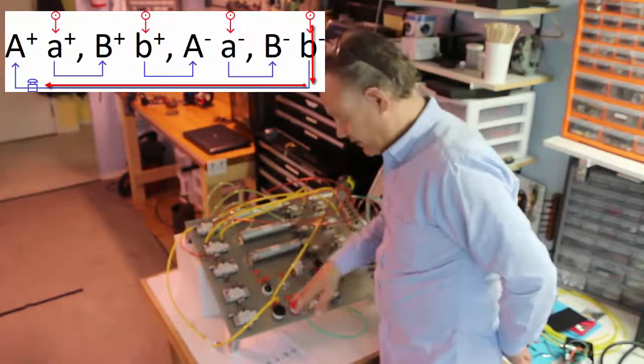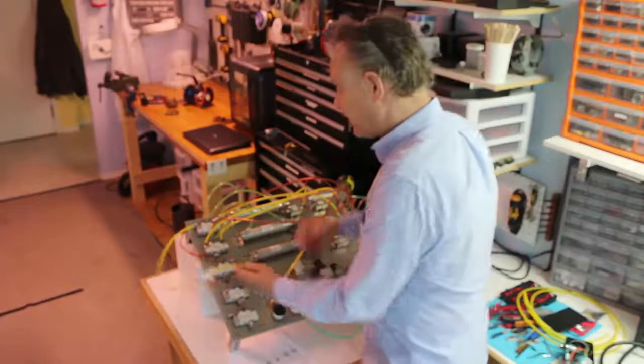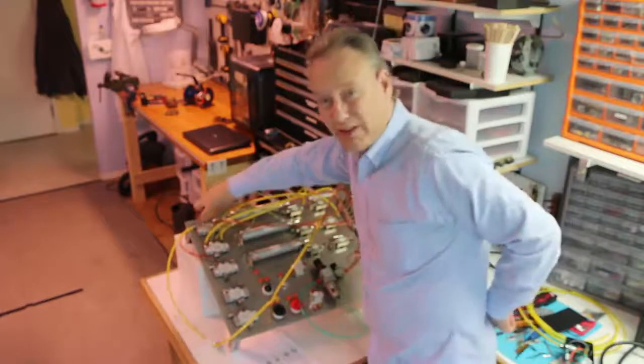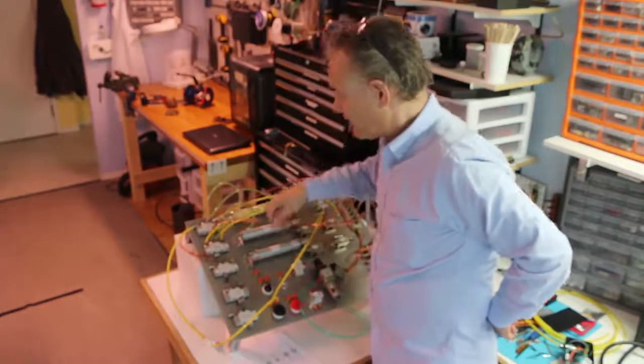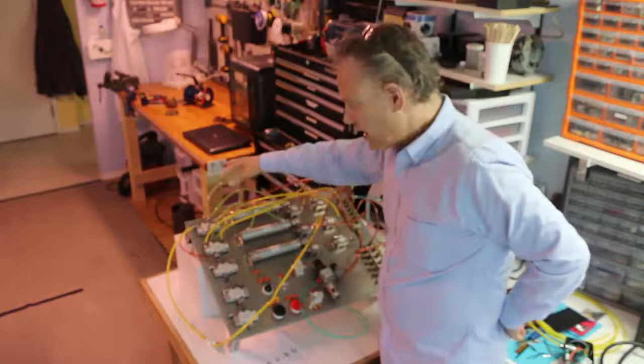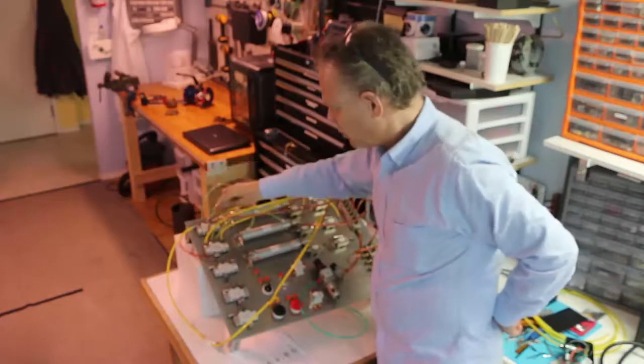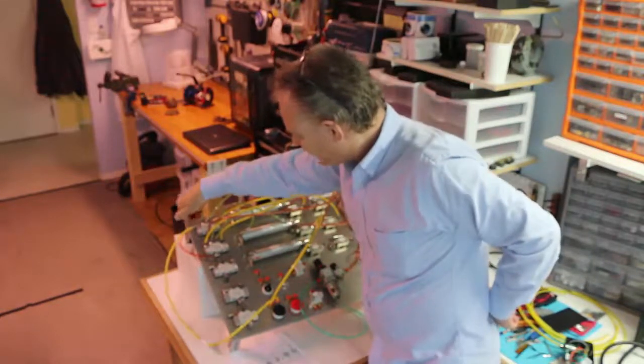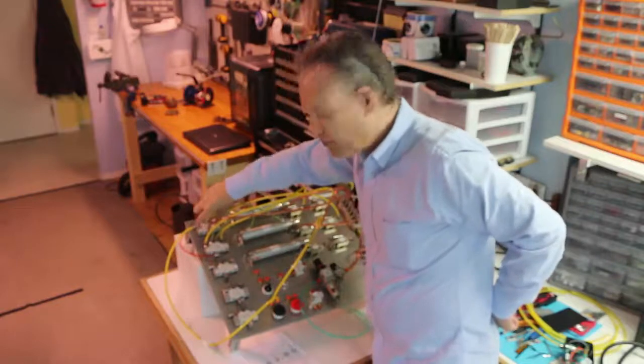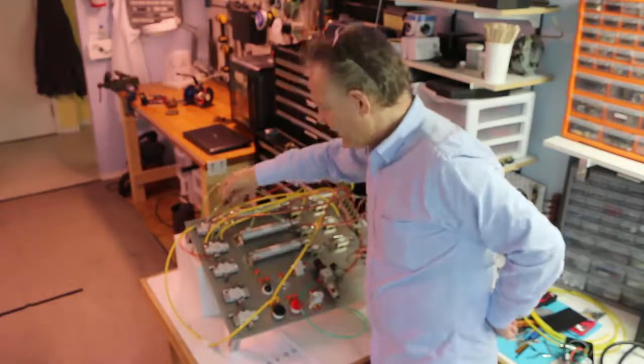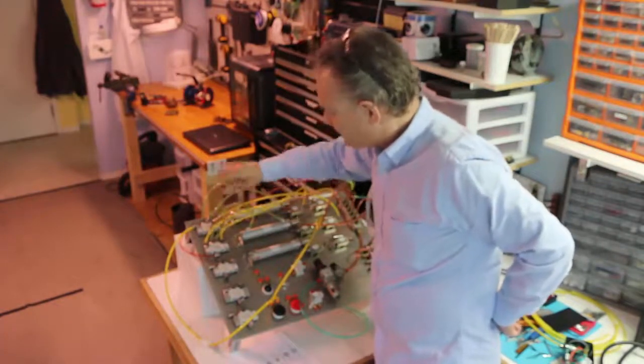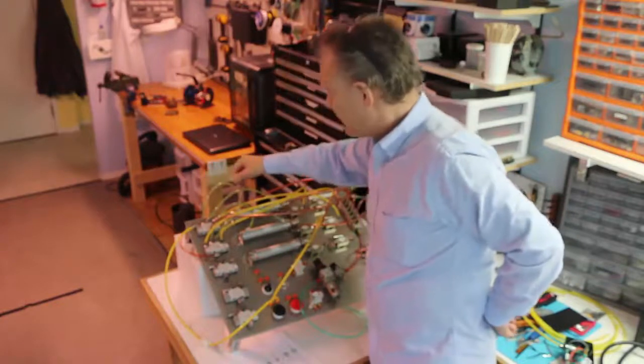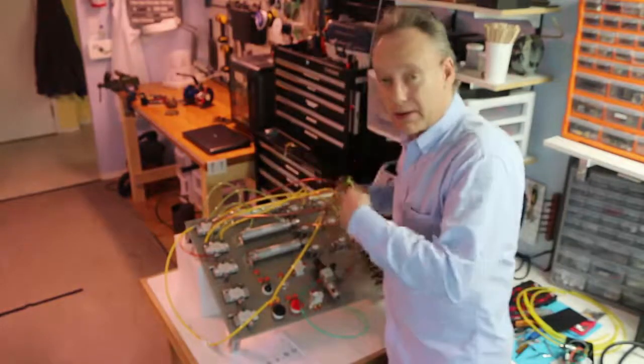Now what's going to happen is that when I press this, air is going to come out of here. It's going to move the spool in this, which is going to make the air from here come out this hose. So when this pilot activates the spool, it pushes the spool over, and then the air from here is coming out here. And then that makes the air go into the cylinder and makes it go out.